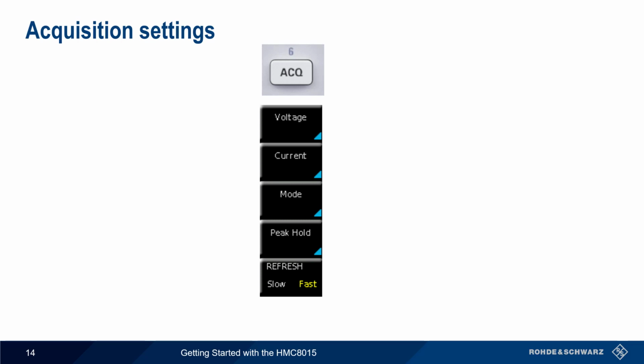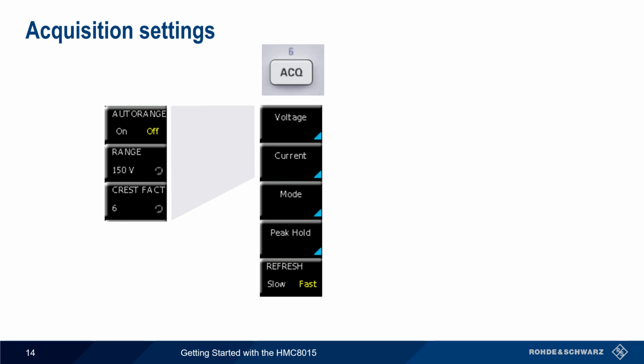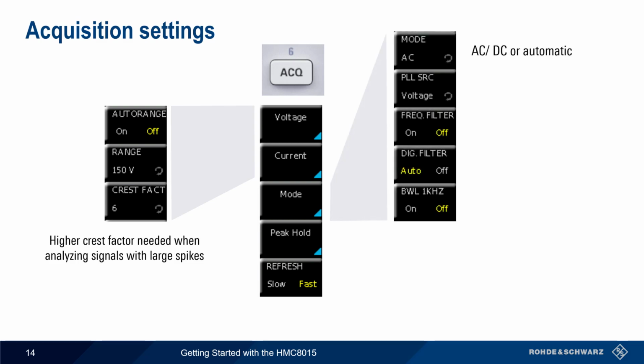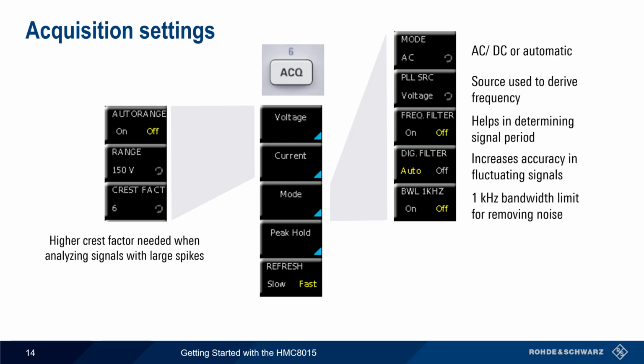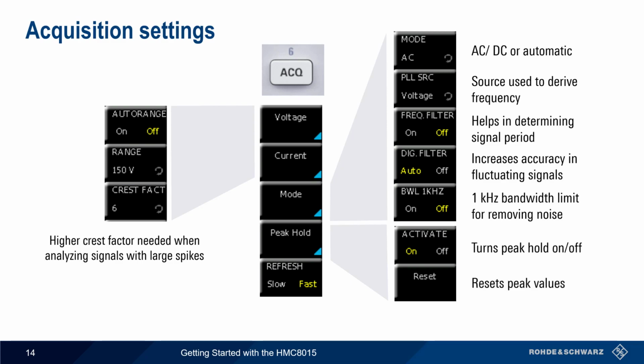In numeric and other modes, the acquisition button provides access to various measurement parameters. The voltage and current buttons can be used to set the range and enable or disable auto-ranging, and crest factor can be increased if needed to measure signals with large spikes. Mode is primarily used to choose whether measurements are made on AC or DC. The HMC can also determine this automatically. Additional mode parameters can be adjusted if necessary, but in most cases the default values are sufficient. The peak hold button can be used to activate the peak hold or to reset the peak hold period. And finally, the refresh rate can be changed from its default of 10 values per second to a single average value every second.